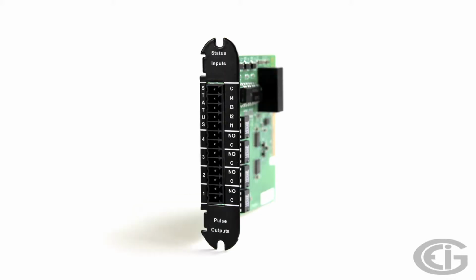The next card is a four-channel pulse output and four-channel digital input card. This card can be used to send pulses like defined value KYZ pulses to another device, or can be used to collect KYZ pulses from something like a water, steam, or gas meter.